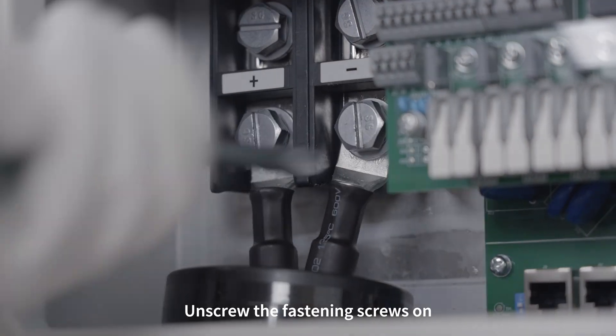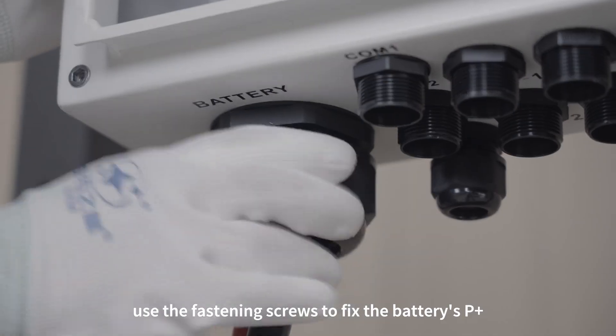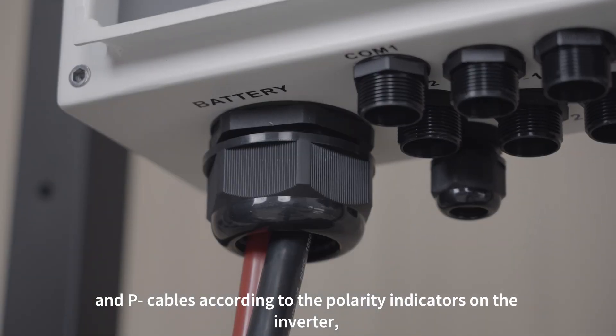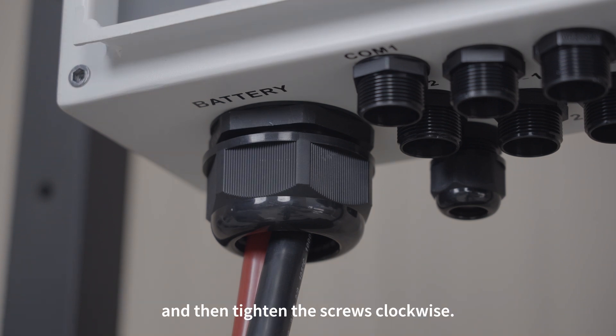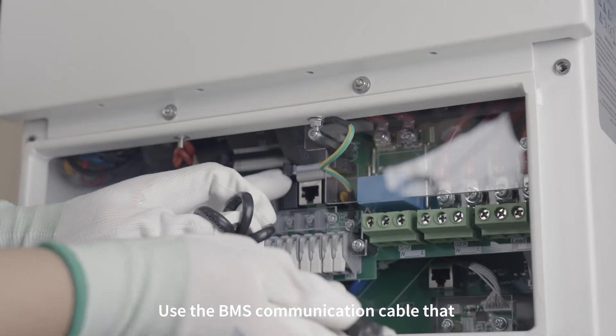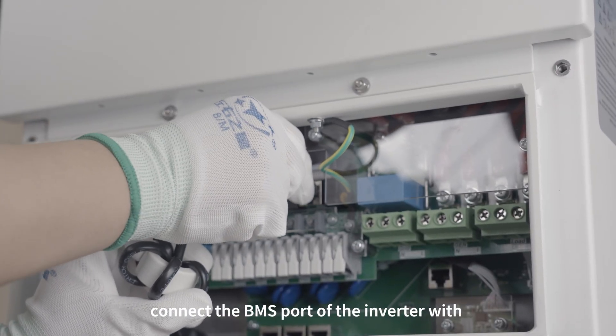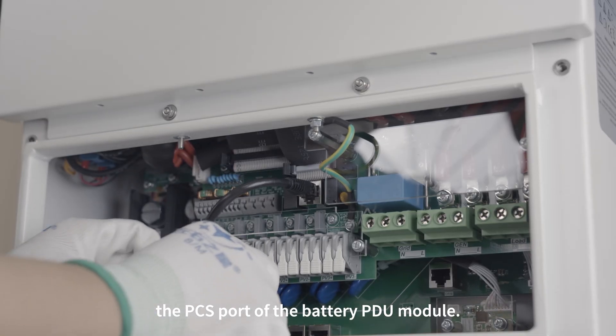Unscrew the fastening screws on the inverter's battery terminals. Use the fastening screws to fix the battery's P+ and P- cables according to the polarity indicators on the inverter, then tighten the screws clockwise. Use the BMS communication cable that has been wrapped around the magnetic ring to connect the BMS port of the inverter with the PCS port of the battery PDU module.